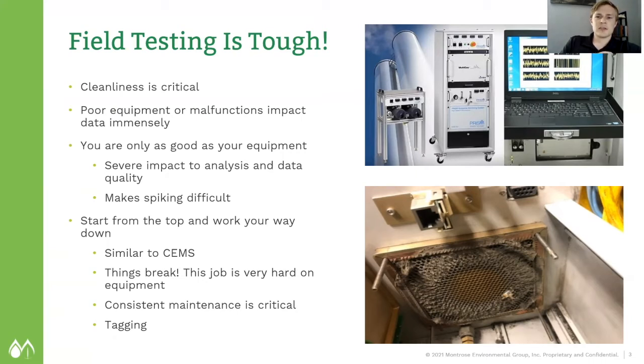And like anything else, to direct your attention to the bottom right picture, we do a lot of servicing of instruments where customers or other firms will send us their FTIRs for maintenance, generally the 2030 MKS model. And things happen over time. You can see in this picture, over probably many years, this FTIR, knock on wood, probably was performing okay, but they noticed that over time, their signal strength would slowly decrease as the ambient temperature increased throughout the day. And they noticed that the fan was dying. Now, this is a really odd and rare problem because those fans should just be cooking all day, every day. And it turns out the fan was fine. It was just being blocked by a tremendous amount of dust and just dirtiness.